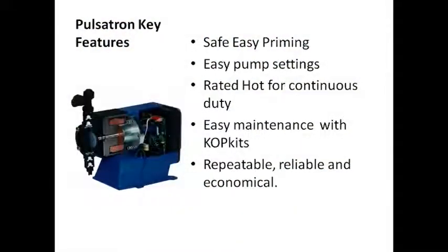The key features of the Pulsatron series metering pump include safe easy priming, easy installation and pump settings, rated hot for continuous duty. This means the pump continues to make its rated output and maximum pressure even at its operating temperature. State-of-the-art double ball guided check valves ensure metering performance. Easy maintenance with KOPkits. The Pulsatron series pumps are repeatable, reliable, and economical.